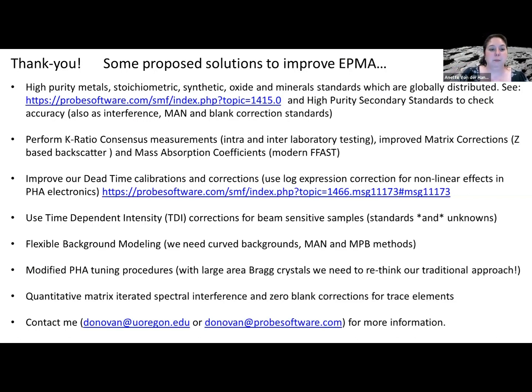When you use a focused beam on a tungsten instrument, it's really 1 micron. You can't focus it much more than that. But I had people who have a field emission instrument now and still use the focused beam settings, and all of a sudden get bad analyses because the beam is actually 20 nanometers, and it's burning a hole in the sample.